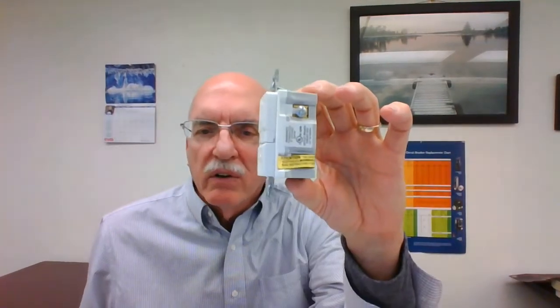Eaton is spelled E-A-T-O-N. Method 5 can be used when you have a fuse panel or maybe a circuit breaker panel in the basement of the home or in the garage of the home that does not have an AFCI model breaker available. In this situation, the code allows a receptacle outlet, and that can protect the whole circuit, but it has certain requirements. With this method of using this receptacle, you can forget any AFCI breaker and just install this receptacle in the first outlet box as long as there's a metallic raceway to said first box.